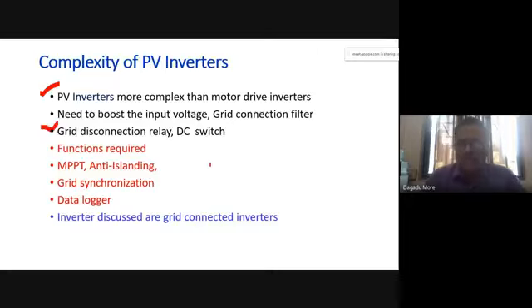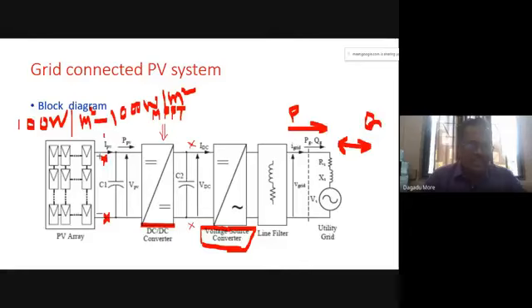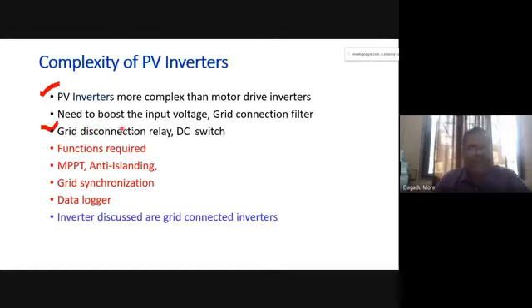At the PV side, we require a DC switch. Here this DC switch is required at the PV side. So the DC switch is here. This is the DC supply. We require a DC switch at the DC side, and a grid disconnection relay. When the grid fails or is off because of some maintenance problem or faults, immediately our PV system should be disconnected from the grid, and for that we require a relay, the grid disconnection relay. The DC switch is required at the DC side.